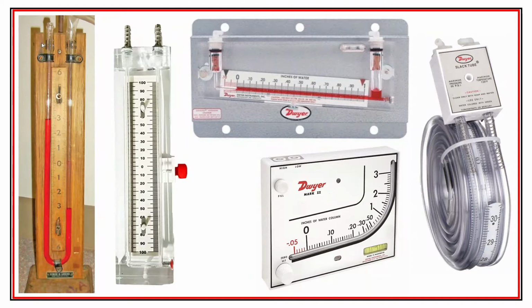So sometimes we might want to measure a pressure compared to atmosphere, or other times we might want to put it on either side of something with air flowing through it. One very common use is to measure whether an air filter is getting dirty, by connecting a manometer to either side of the filter. There's pressure on one side, and then the pressure on the exit of the filter. As that filter gets dirty, that differential pressure increases, and you can tell by way of the manometer. That could be a very, very small incremental change in pressure, so the manometer is really useful for that.